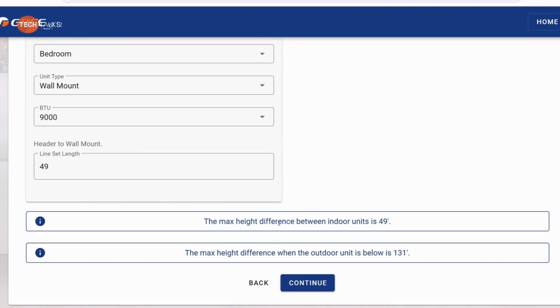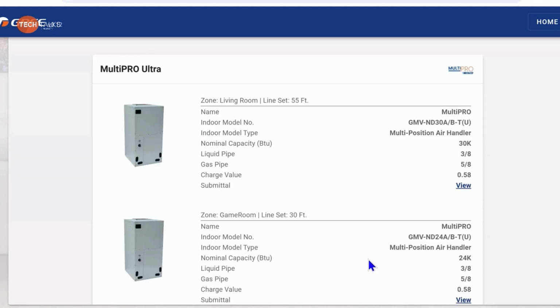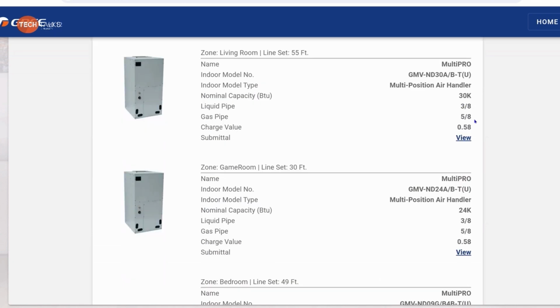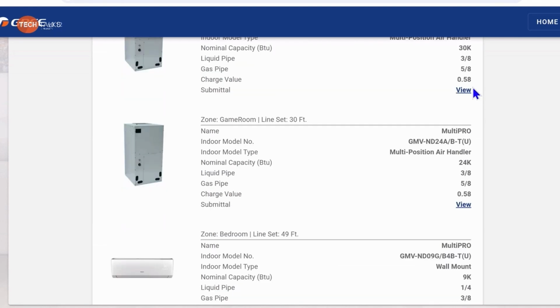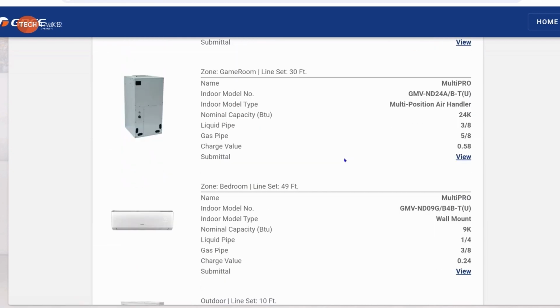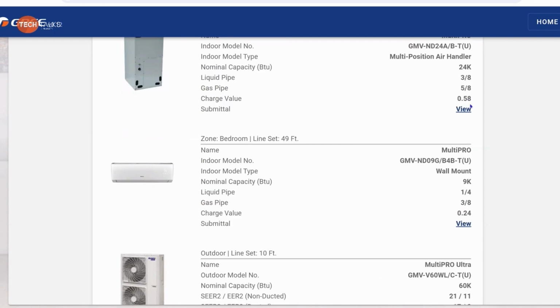And it gives these warnings. Max height difference between indoor and outdoor units is 49 feet. Max height difference between the outdoor unit is 131 feet. It's just kind of some warnings there. All right. So we've got the 2.5-ton air handler. Its line set size is 3/8, 5/8. The charge value per foot for the 3/8 pipe is 0.58. You can actually click right here and it takes you right to the submittal for that unit. Then we have the 2-ton air handler. That's 3/8, 5/8. And the charge amount for that unit is 0.58.